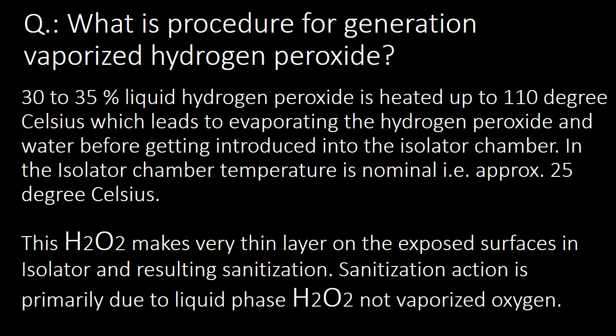This lower temperature causes hydrogen peroxide to return to the liquid state. The H₂O₂ makes a very thin layer on the surfaces where it gets exposed, resulting in sanitation. The sanitation action is primarily due to the liquid phase of hydrogen peroxide, not the vaporized phase.